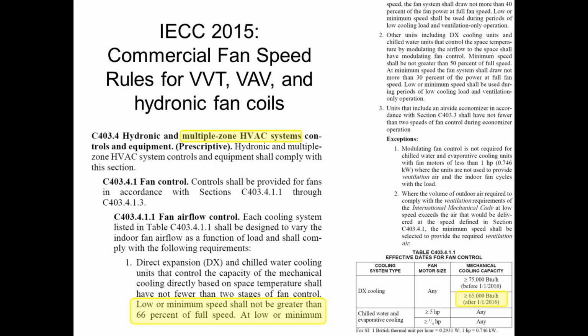But if I have a zoning system, I'm going to have to put the multiple speed fan on, assuming it's more than 65,000 BTUs, which is essentially a 6-ton rooftop and up, 5.5 tons and up. So 6-ton rooftop and up. So keep that in mind on there.